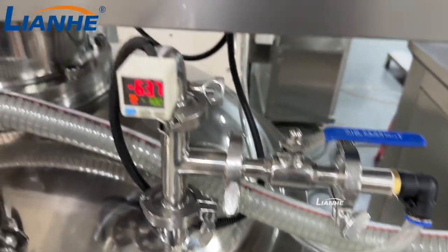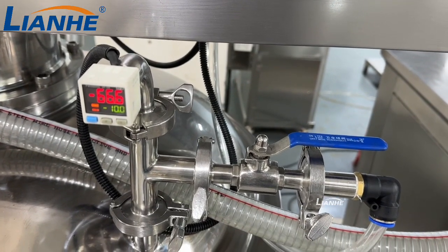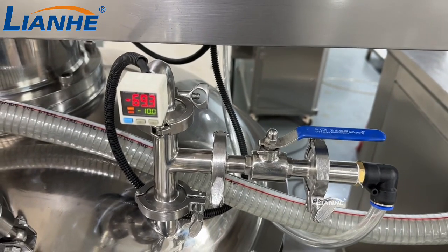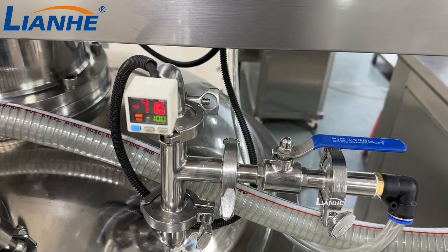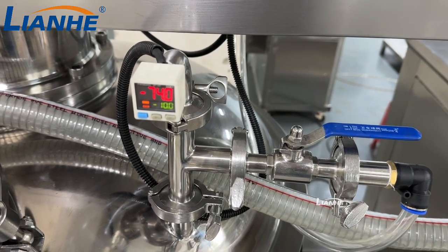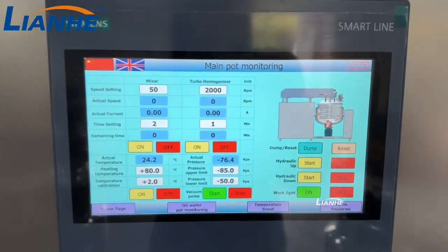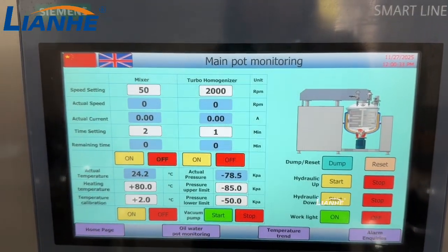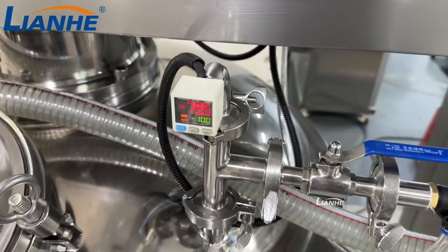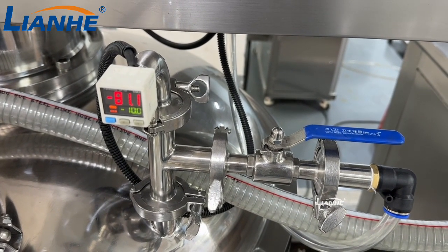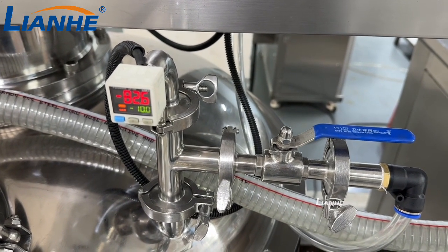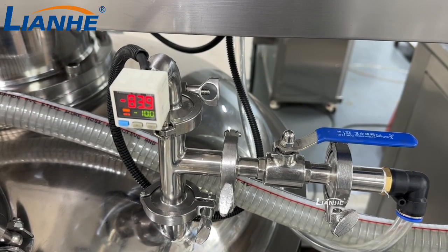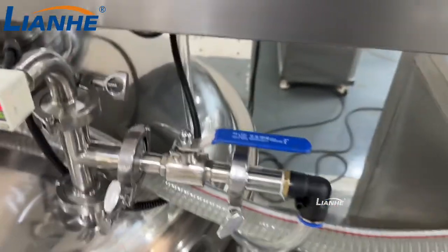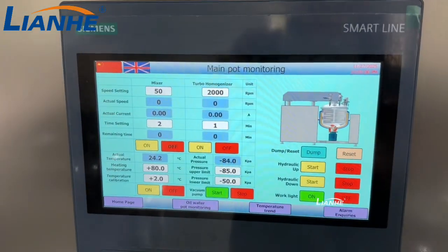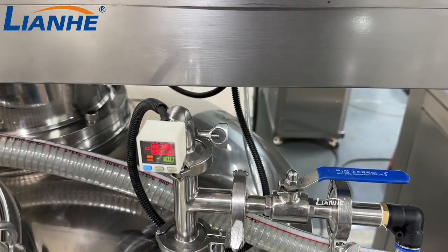There, water comes here. So check the PLC screen. The actual pressure is also changing too. And also now the pressure. The vacuum function will stop automatically when it arrives at -85. And then now the pressure is going down.